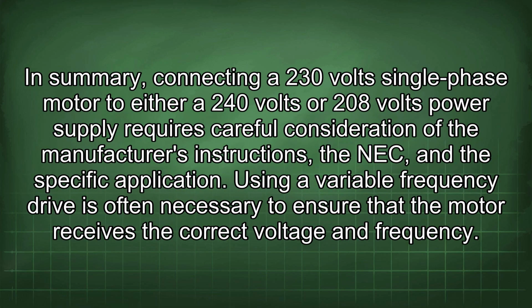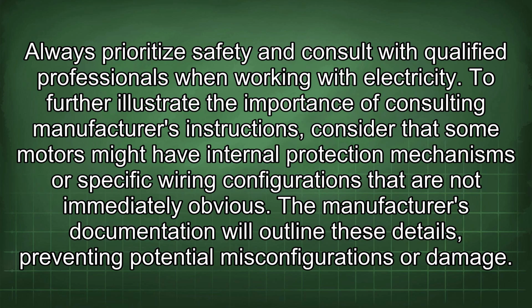In summary, connecting a 230-volt single-phase motor to either 240 volts or 208 volts power supply requires careful consideration of the manufacturer's instructions, NEC, and the specific application. Using a variable frequency drive is often necessary to ensure that the motor receives the correct voltage and frequency. Always prioritize safety and consult with qualified professionals when working with electricity. To further illustrate the importance of consulting manufacturers' instructions, consider that some motors might have internal protection mechanisms or specific wiring configurations that are not immediately obvious. The manufacturer's documentation will outline these details, preventing potential misconfigurations or damage.